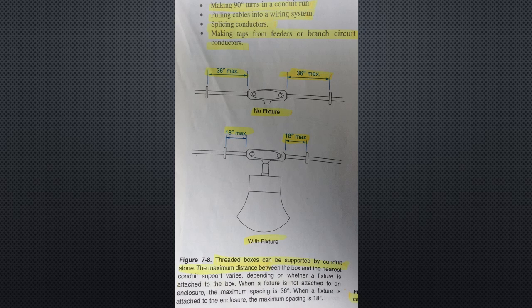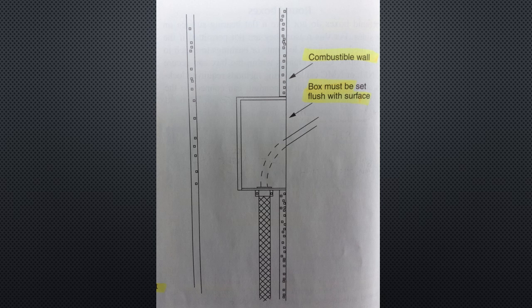Threaded boxes with a volume less than 100 cubic inches may be supported by conduit alone. Two conduits threaded wrench tight into the enclosure are considered adequate support. Figure 7-8 on the screen illustrates the maximum spacing between the box and the nearest conduit support. Boxes and enclosures can be mounted using nails or screws. If nails pass through the interior of the enclosure, they must be located within a quarter inch of the end or back of the box. If a box is located in combustible material, it must be installed flush or project from the surface. If installed in a non-combustible material, the box may be set back a quarter inch from the surface. See Figure 7-9, part of which is shown on the screen.